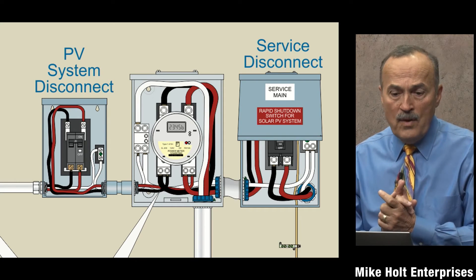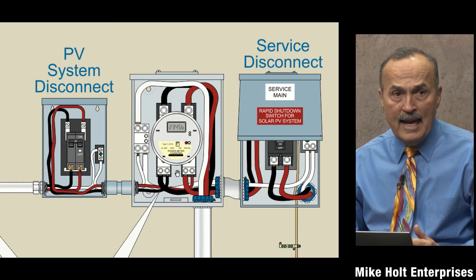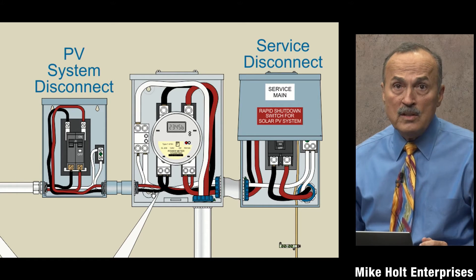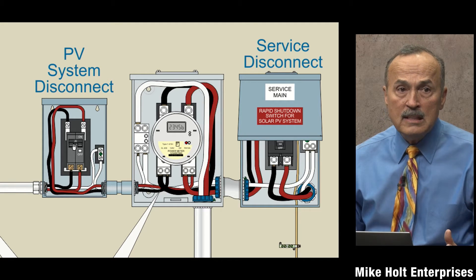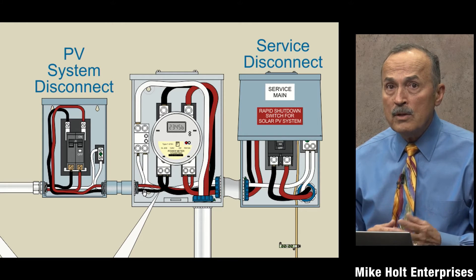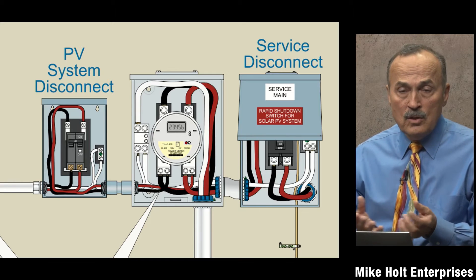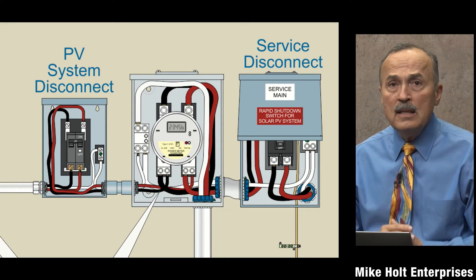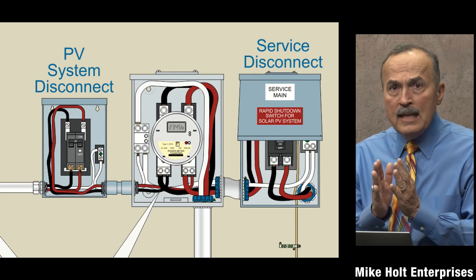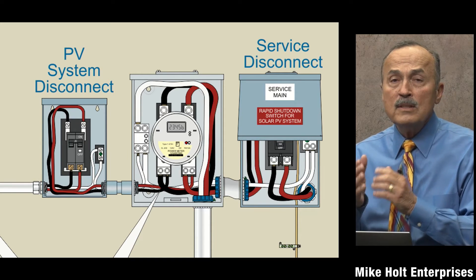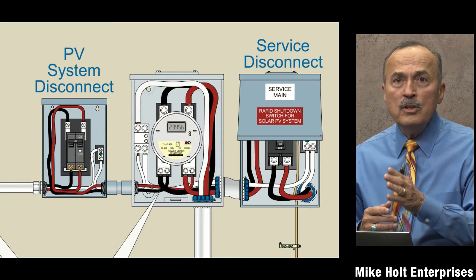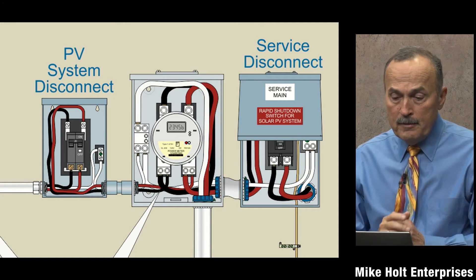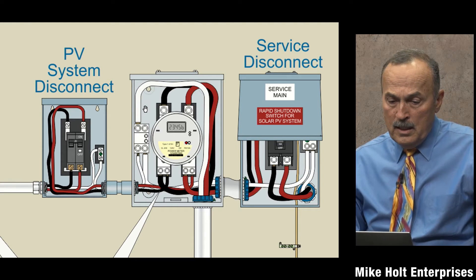This is not directly 705, but it's related: when making a supply side connection, the conductors going into the PV system disconnect are not service conductors as per the Article 100 definition. Service conductors, per Article 100, are those from the utility that terminate at the service disconnecting means. So this PV disconnect is not a service disconnect, and these are not service conductors.